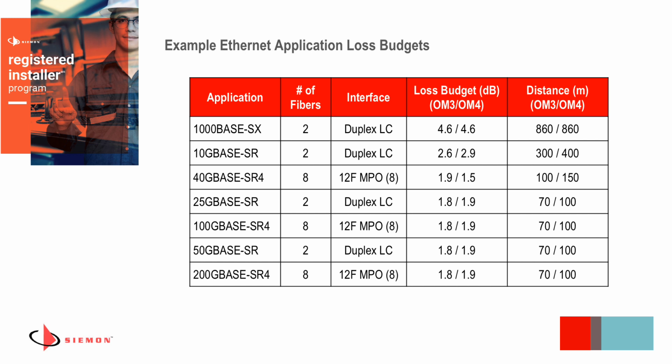So it's important to be aware of those higher speeds and lower losses. So you really want to limit your lengths. Even though you can run gigabit out to 860 meters, that's not going to support 10 gigabit or 40 gigabit. So you really want to design systems ideally around OM4, which has that 100 meter supported distance. And if you can get losses less than 1.9 dB on your system, with the exception of 40G base SR4, which is an MPO system, then you're going to be in good shape moving forward all the way through.